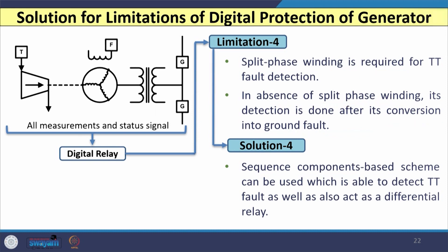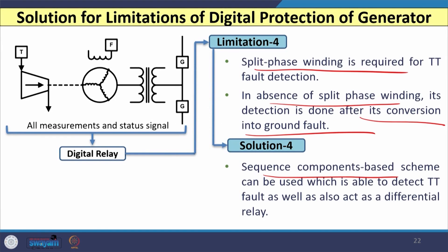The solution for the fourth limitation is to use sequence components-based schemes capable of detecting both stator faults and turn-to-turn faults as a single unit. In this lecture, we discussed backup protection, stator and rotor ground fault protection, out-of-step protection, loss of field protection, over-frequency and under-frequency protection, and the problems and partial solutions for digital relay limitations. Thank you very much.